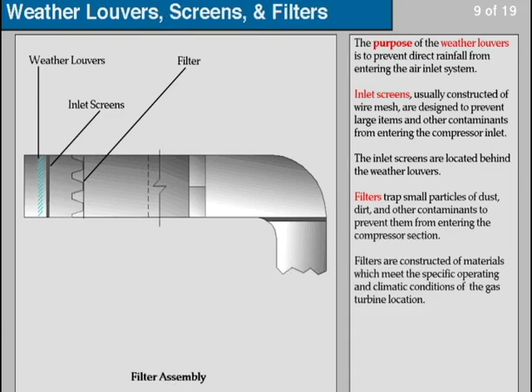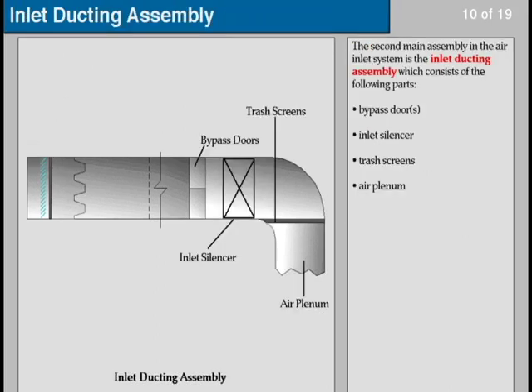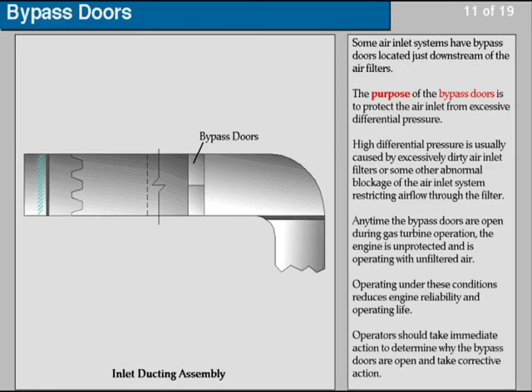Filters are constructed of materials that meet the specific operating and climatic conditions of the gas turbine location. The second main assembly in the air inlet system is the inlet ducting assembly, which consists of the following parts: bypass doors, inlet silencer, trash screens, and air plenum. Some air inlet systems have bypass doors located just downstream of the air filters. The purpose of the bypass doors is to protect the air inlet from excessive differential pressure, which is usually caused by excessively dirty air inlet filters or some other abnormal blockage of the air inlet system restricting airflow through the filter. Any time the bypass doors are open during gas turbine operation, the engine is unprotected and is operating with unfiltered air.